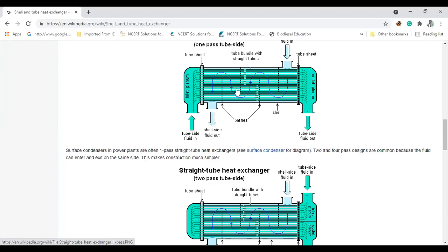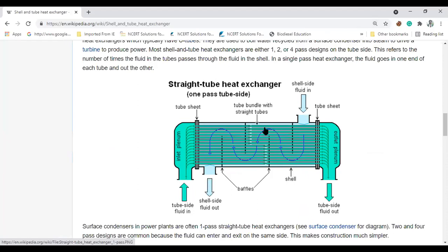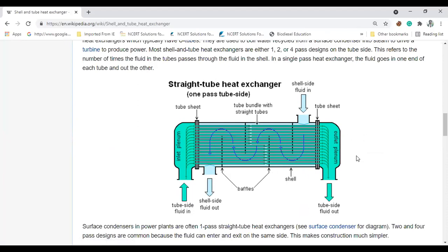If there were no baffles, the fluid would go straight across. So I give a restriction over the flow, and it moves in a specific path using the entire area of the tube sheet. The design must withstand a specific operation for a given pressure drop. You will have different pressure drops on the tube side and on the shell side.